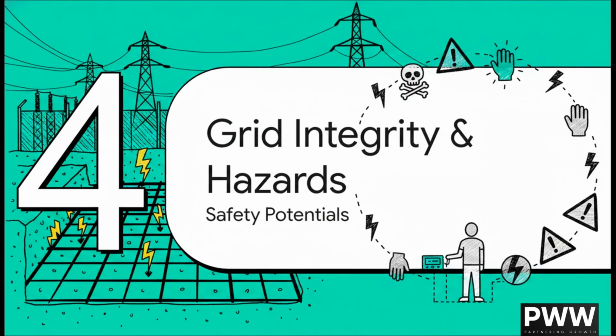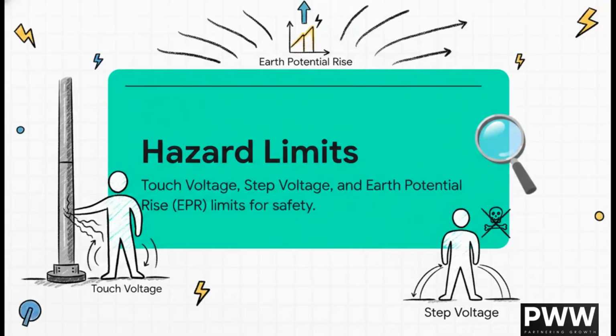Which brings us to Section 4, Grid Integrity and Hazard Potentials. So, according to IS 3043, Clause 10, and IEEE 80, our primary design criteria aren't just ohms, they are hazard limits. Touch voltage is the potential difference between a grounded metallic structure a person is touching and the earth right under their feet. Step voltage is the potential difference between a person's 2 feet on the ground during a fault. And earth potential rise, or EPR, is how high the voltage of the entire grid jumps relative to remote earth. Modern compliance is all about ensuring these specific potentials stay strictly within safe human thresholds during an active fault.